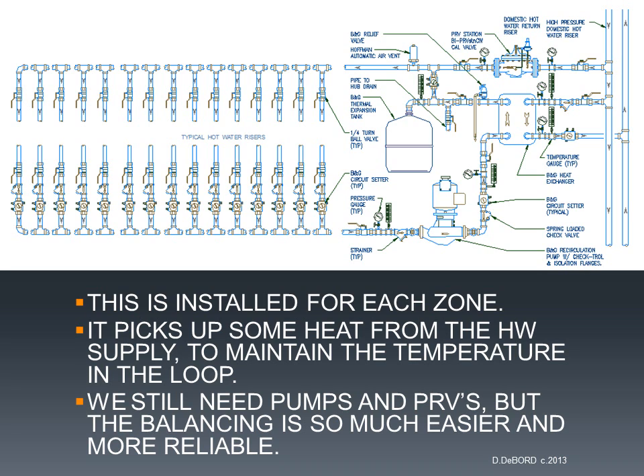So for each one of the zones, it has its own heat exchanger, a plate and frame heat exchanger, and it's getting the heat to maintain the hot water temperature in the loop by picking up some heat from the hot water supply loop. Okay, so it's stealing a little bit of hot water, but not that much. A little bit of energy is coming off there, but it's still a very efficient system. So this is installed on each zone. Again, it picks up some of the heat from the hot water supply to maintain the temperature in the loop.